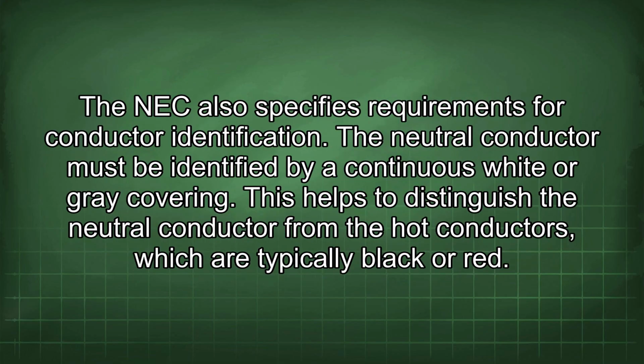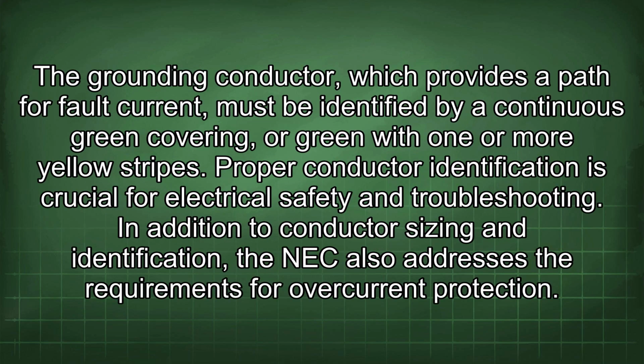The NEC also specifies requirements for conductor identification. The neutral conductor must be identified by a continuous white or gray covering. This helps to distinguish the neutral conductor from the hot conductors, which are typically black or red. The grounding conductor, which provides a path for fault current, must be identified by a continuous green covering, or green with one or more yellow stripes. Proper conductor identification is crucial for electrical safety and troubleshooting.